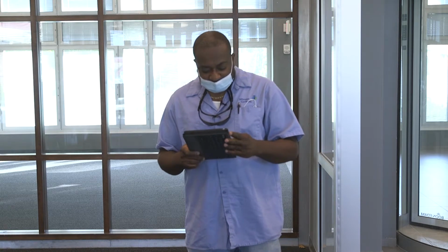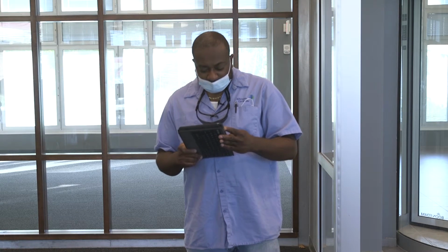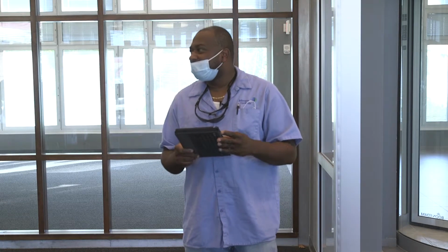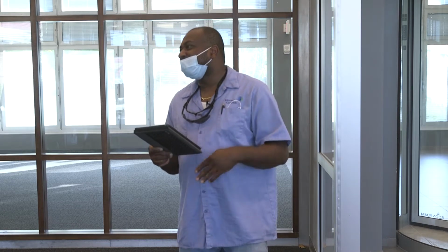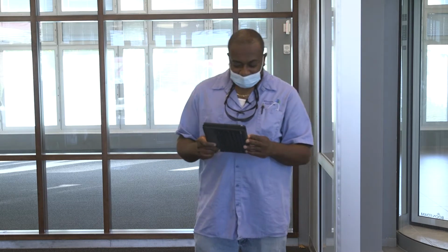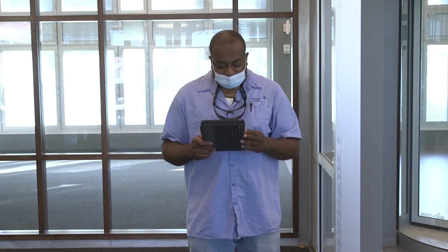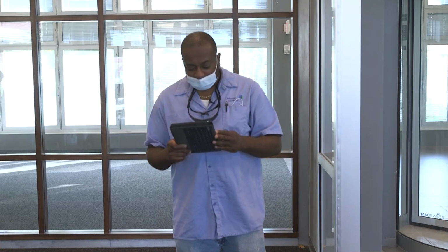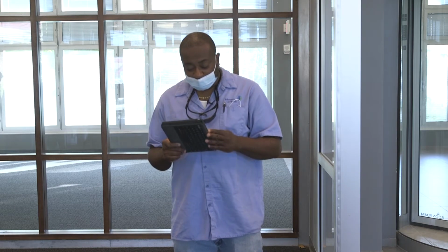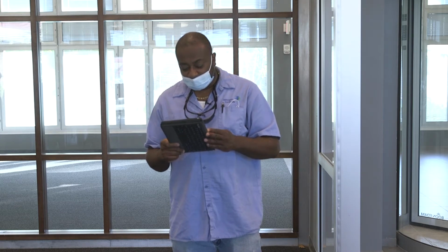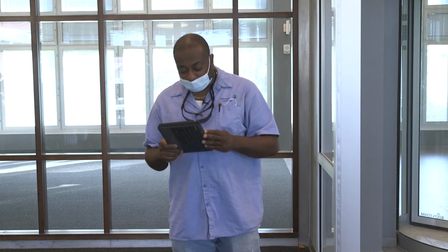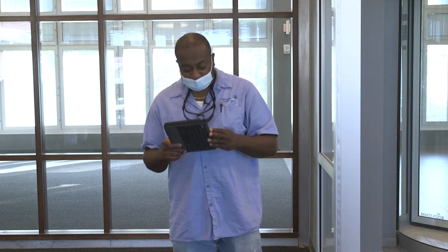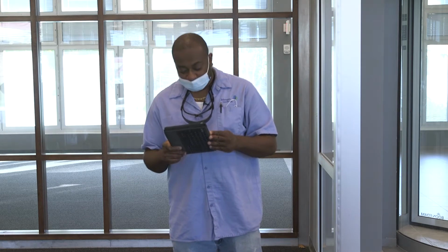Intermittent blower is to set the room thermostat fan switch to auto. Continuous blower, you set it on. For intermittent blower, the blower only comes on when there's an actual call for cooling or heating. So set the room thermostat fan switch to auto and set the system switch to auto or heat. During a call for cooling or heating, the 24-volt signal is provided to the G1 terminal directly from the thermostat or from the condenser or heat.